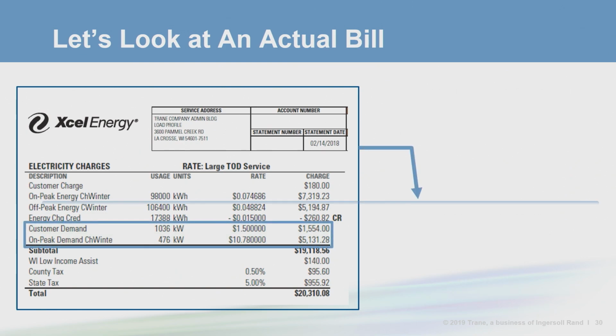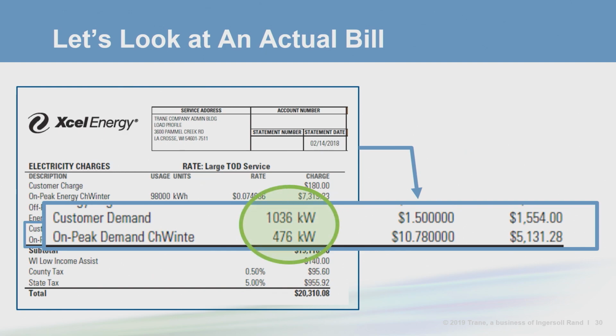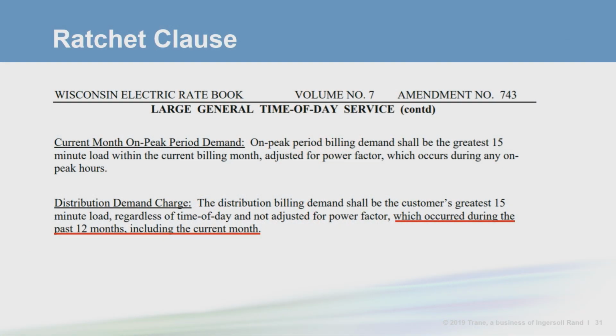As you can see here, not only are the dollar values different, the kW values are different as well. The on-peak demand sits at only 476 kW, but the customer demand is more than double that at 1,036 kW. What's that all about? This is called a ratchet, and to understand demand ratchets, we need to take a look at the utility tariff. Here are a few paragraphs that we've cut and pasted from the Xcel Wisconsin tariff.